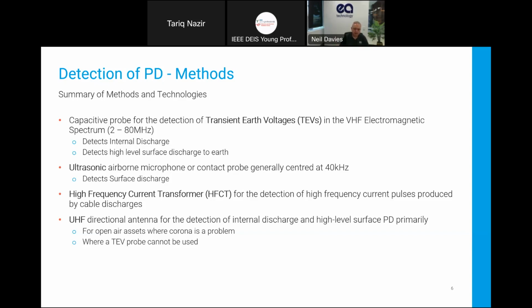Another technique that is quite widely used, and more used on cable systems but certainly can also be used for detecting problems on switchgear as well as cables, is using high frequency current transformers. These would be typically installed around the earth screen of a cable termination, if you can get access safely, of course. They will also detect the high frequency current pulses produced from the cable discharge, or if you put a high pass filter in there, they will also detect stuff that's local in the switchgear itself.